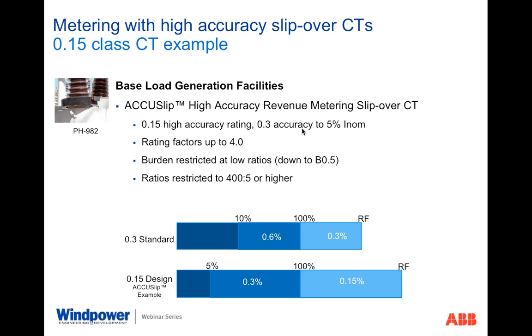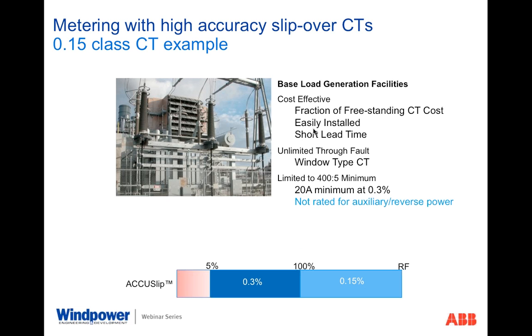So in this application, we're really able to provide excellent metering performance on all those baseload facilities that during deregulation had to be separated from the transmission grid operator via a metering point. So that was extremely important in locations connecting to PJM or ERCOT out there in terms of the ISO requirements. Going forward with that configuration, another reason why it was important was some of those products also took a different form to make them easier to install.